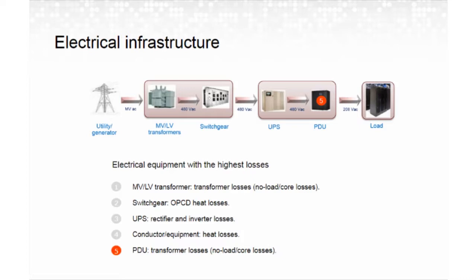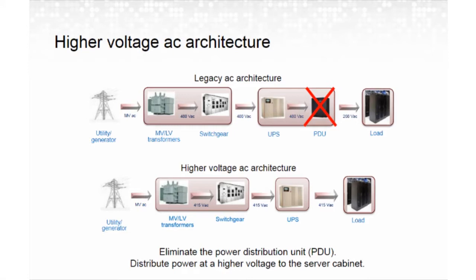Thanks, Rich. Yeah, so basically a PDU or a transformer, you know, it's basically 480 to 208 or your usage voltage. In the data center, a PDU is basically a power distribution unit where there's a transformer and some distribution built into a box. And as Rich talked about before, it's in essence a transformer, so there are core losses and no-load losses. One of the things we were looking at from the data center world is trying to eliminate that, if we could, with a higher voltage AC architecture.